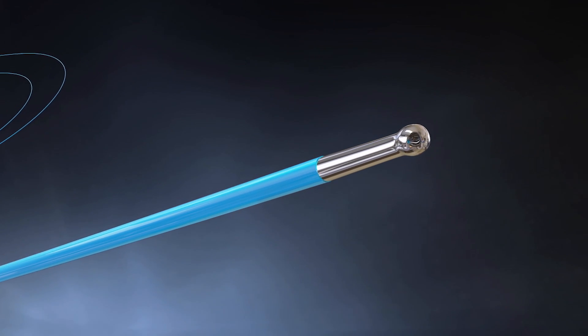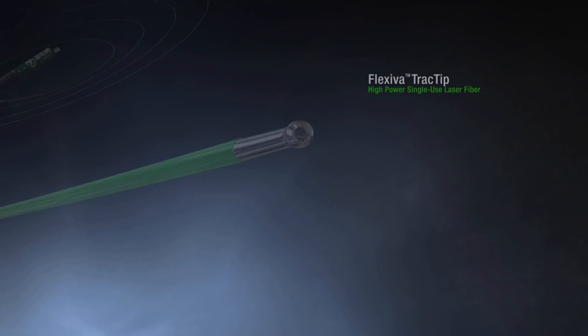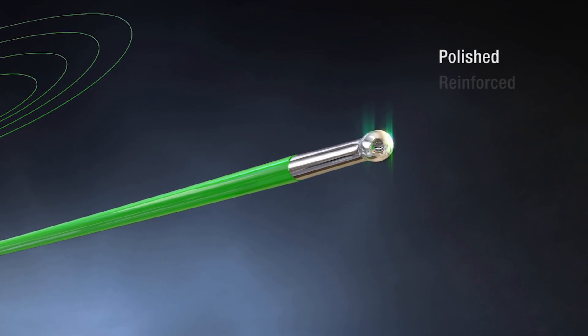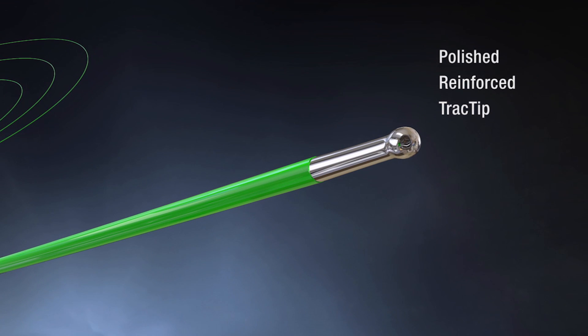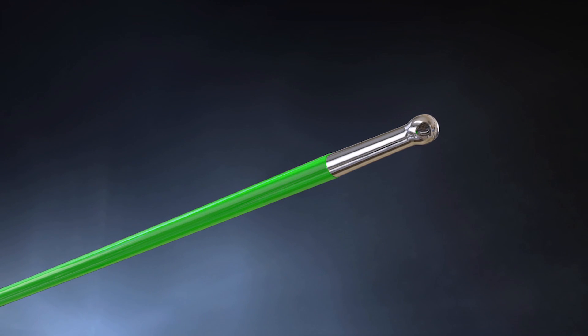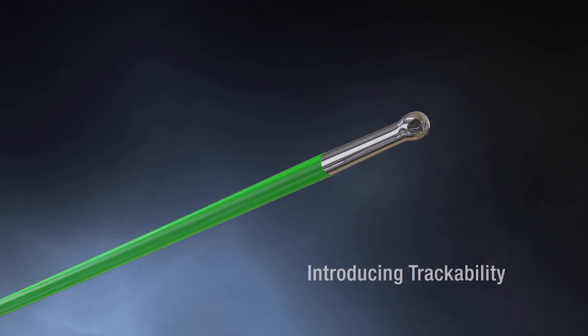Boston Scientific's AccuTrack and Flexiva TracTip Laser Fibers are equipped with a polished and reinforced ball-shaped output tip. They are the first Holmium laser fibers designed to reduce procedure steps by allowing for trackability through a flexible ureteroscope.